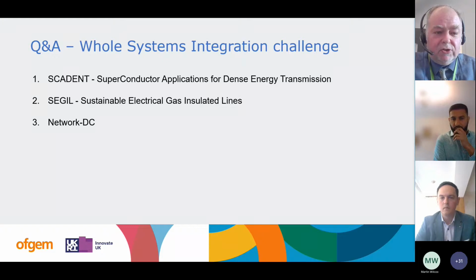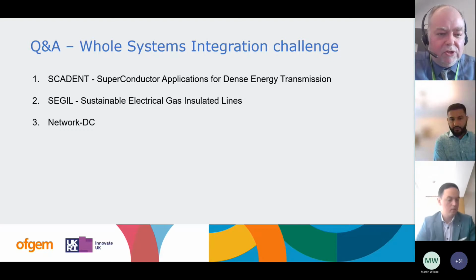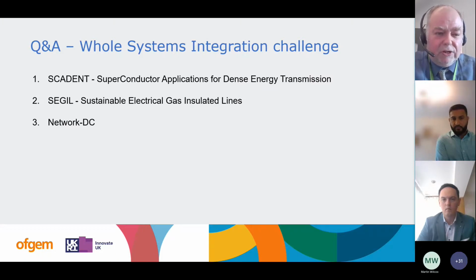Unlike perhaps the Chinese examples where an overhead line fault is a network in parallel with their own—as long as they can deal with the temporary timeframe of seconds for stability, thermal and voltage, that would be fine—in GB we're taking off a lot of generation in that timeframe, so we can't really afford to do it. So switching stations are helpful: you have selectors on the AC system, which give you operational control for taking outages and allow expansion. It's really in that context that selectors would be involved in a DC network, but you'd still need the DC circuit breakers if you wanted a large capacity network, as we've been investigating.